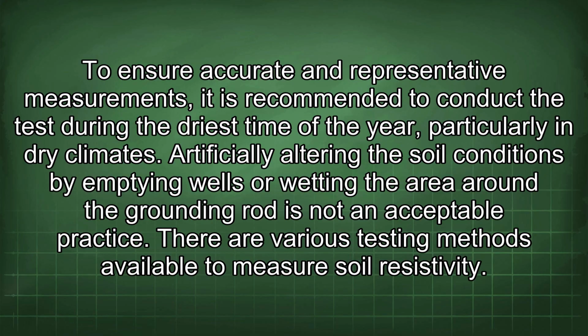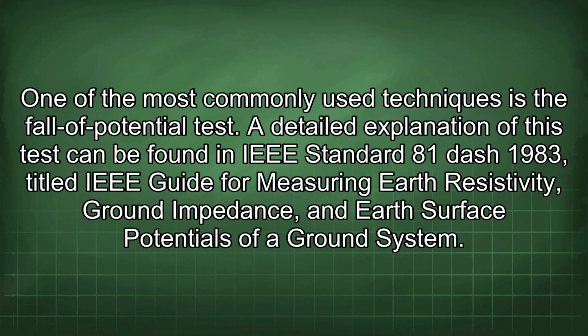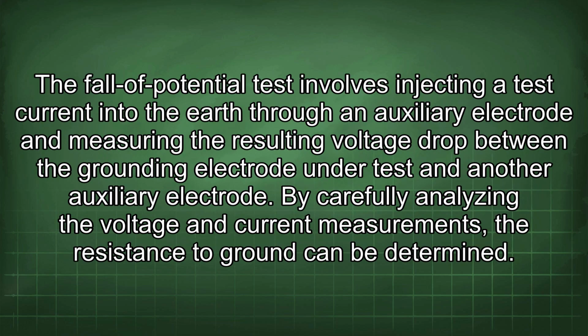There are various testing methods available to measure soil resistivity. One of the most commonly used techniques is the fall of potential test. A detailed explanation of this test can be found in IEEE Standard 81-1983, titled IEEE Guide for Measuring Earth Resistivity, Ground Impedance, and Earth Surface Potentials of a Ground System. The fall of potential test involves injecting a test current into the earth through an auxiliary electrode and measuring the resulting voltage drop between the grounding electrode under test and another auxiliary electrode. By carefully analyzing the voltage and current measurements, the resistance to ground can be determined.